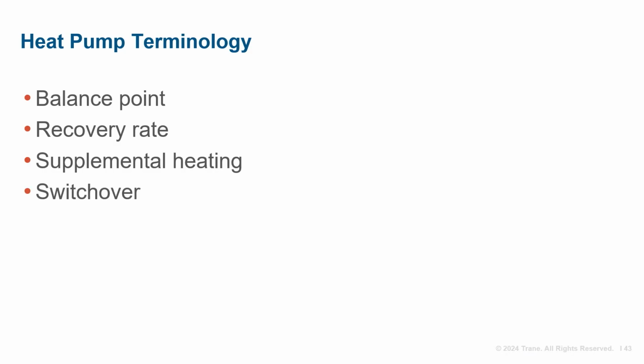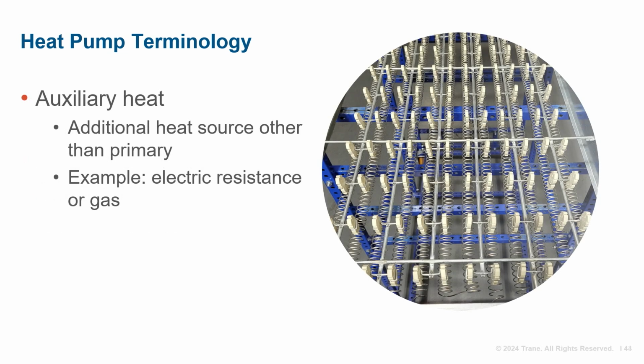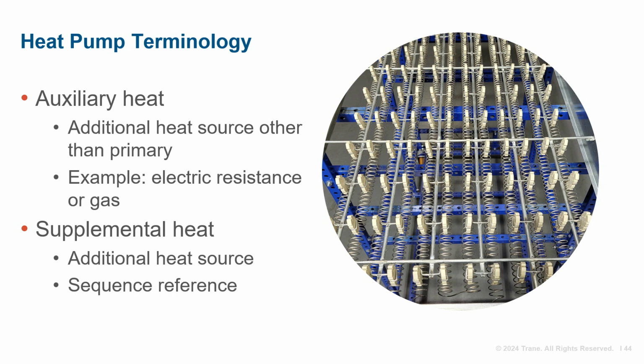The switchover sequence takes place when the outdoor temperature is equal to or less than the heat pump heating lockout set point. In this mode, the compressor heating outputs will be disabled and the auxiliary heating is used to temper the space. The auxiliary heat may be any form of heat other than the primary heat type. In this case, we reference both electric resistance and gas heat options. The supplemental heat term is closely related when referencing auxiliary heat.